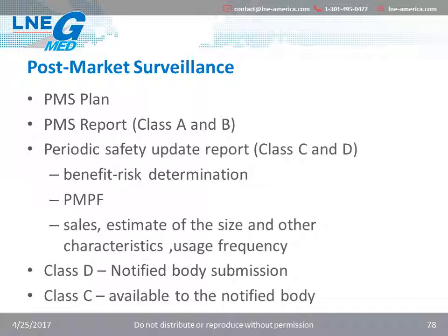The safety report must be updated annually and included in the technical documentation. For Class D devices, the periodic safety update report must be submitted to the notified body electronically for evaluation. For Class C devices, the safety report must be made available to the notified body and competent authority upon request.